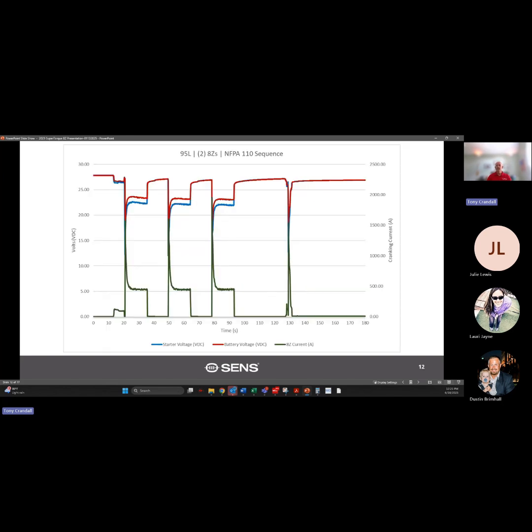This next slide looks at a 95-liter engine, which is a 3 megawatt generator. This one has two 8Zs connected to it, and it's a traditional NFPA 110 style testing sequence. Once again, there is no AC charging source connected to the battery, and initially we had the fuel starting solenoid shut off so the generator would not actually start.